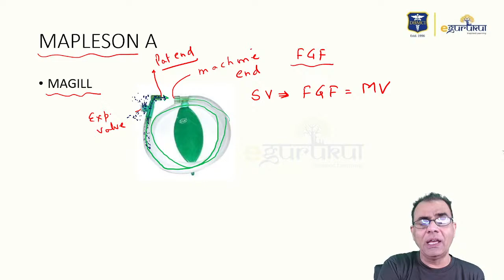Meaning, if the patient is spontaneously breathing, how many liters of fresh gas do you need to give? Minute volume is how much? 6 liters. So you have to give 6 liters. Out of this 6 liters, 75% should be nitrous oxide and 25% should be oxygen. So 75% of 6 liters means how much? Around 4.5 liters. So you will provide 4.5 liters of nitrous oxide and 1.5 liters of oxygen. That is how I told you to set the flow rates. So the setting of the flow rate will depend on which circuit you are using, and whether the patient is spontaneously breathing or on controlled ventilation. Fine.